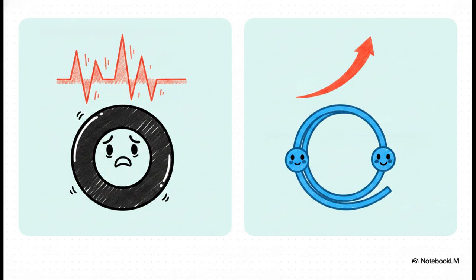Well, there's a fascinating divide in the technology here. Traditionally, the industry has relied on conventional current transformers, or CTs. These use a wound core or a multi-core bushing bar, but they have a major physical vulnerability. Because they rely on a ferromagnetic core, they can actually saturate during massive fault spikes. That essentially temporarily blinds your protection system right when you need it the most.